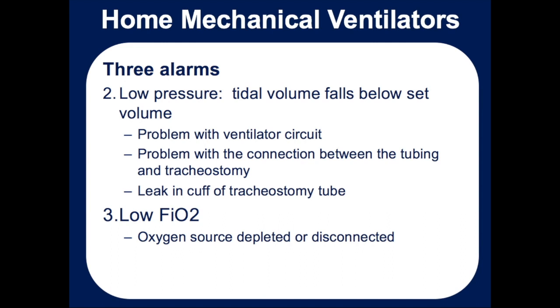The next alarm you might see is low pressure. What this is saying is the tidal volume, which is the amount of air delivered to the lung with each breath, is falling below the volume that it should be. Typically this means there is a problem with the machine or the equipment. If the tubing isn't connected properly, the machine is trying to push in a set amount of air, and that air is not making it to the patient.